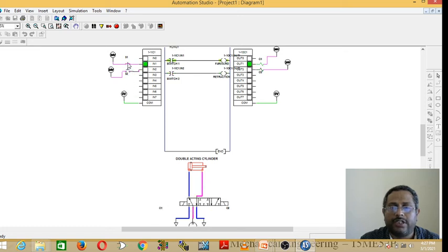Like that, we can control the movement of the piston, whether forward or backward. Means when you operate S1, this switch 1 contact will be closed and this forward coil will be energized, and it will energize solenoid 1, O1, which in turn supplies power to the solenoid operated DCV, and this will move forward and supply air with high pressure to this end and move the piston forward.